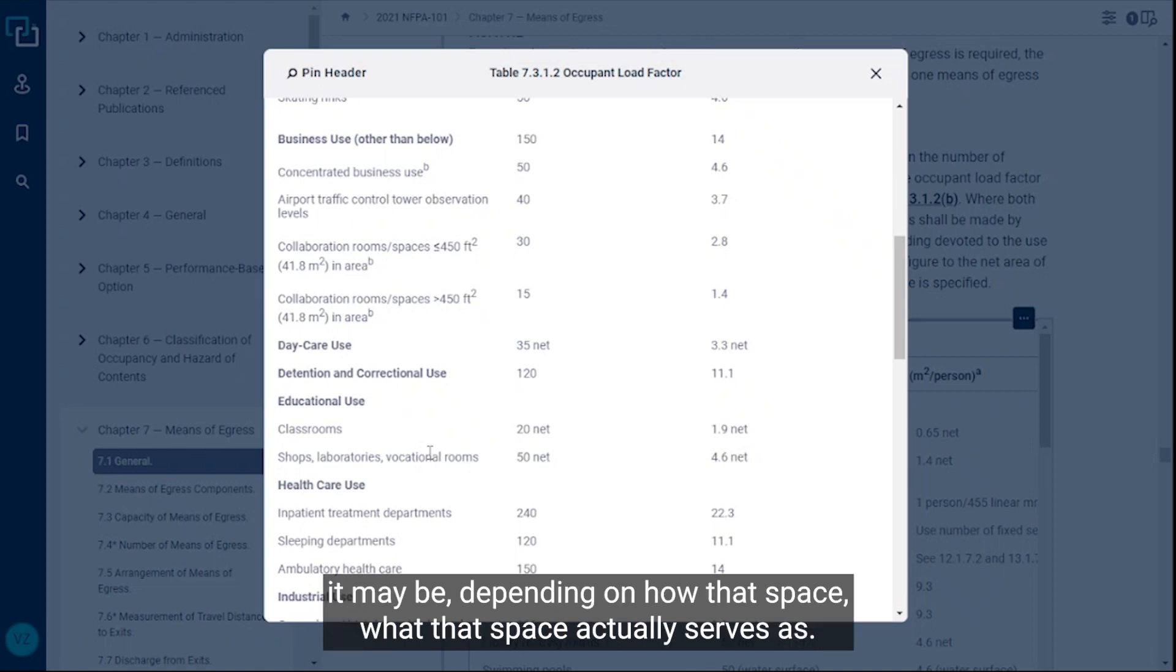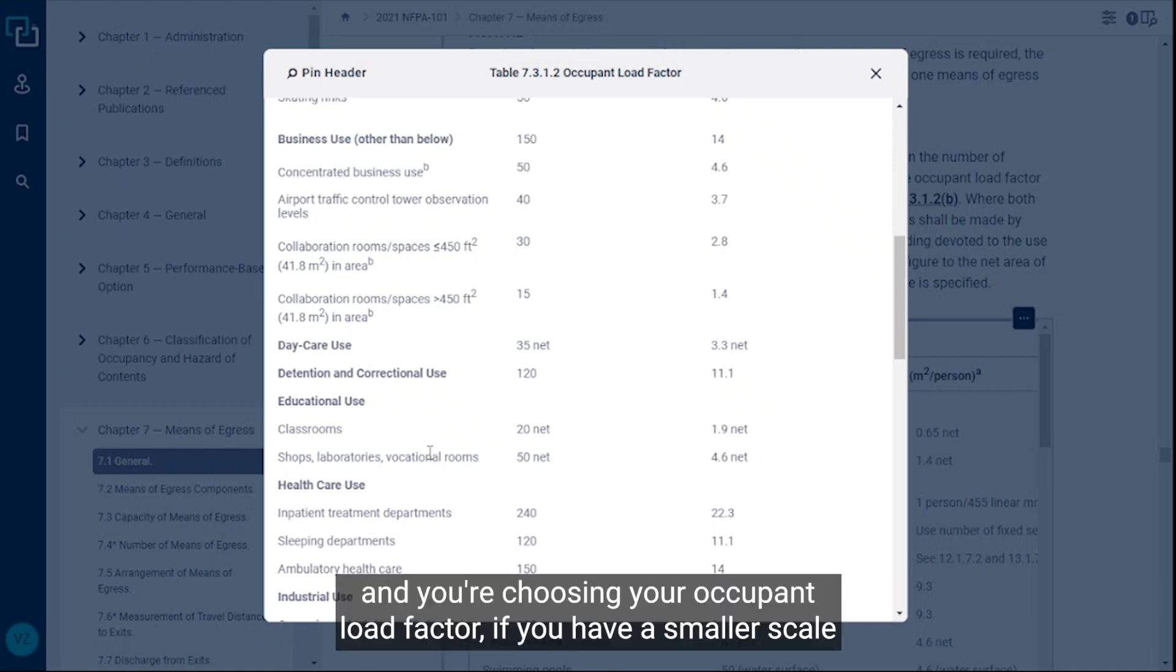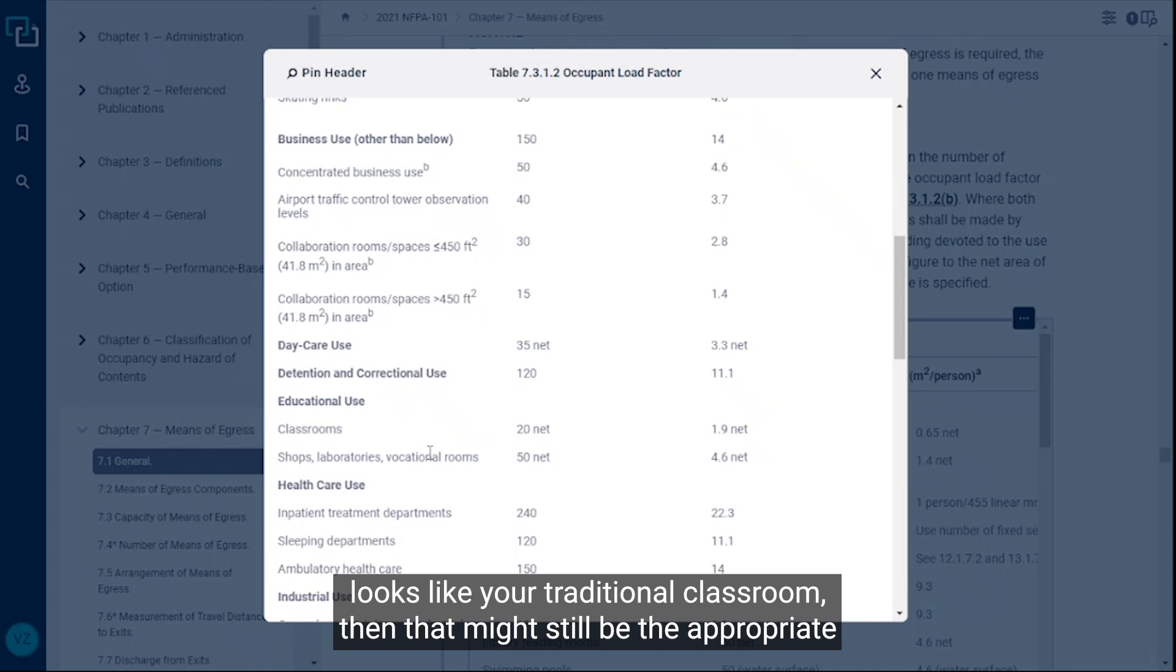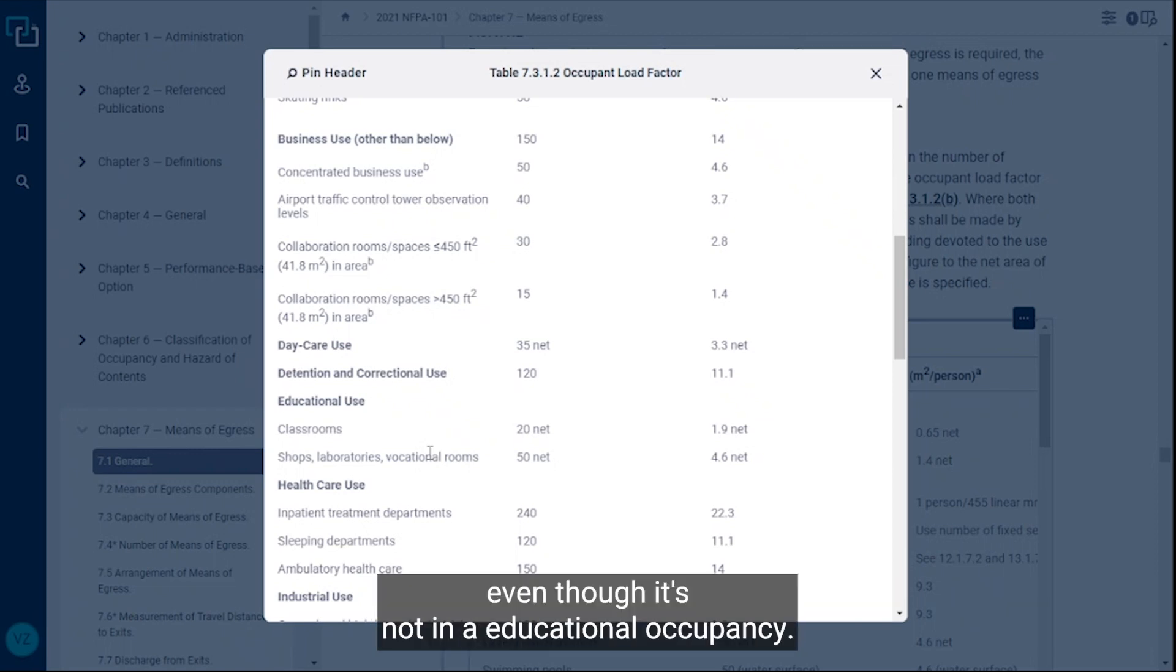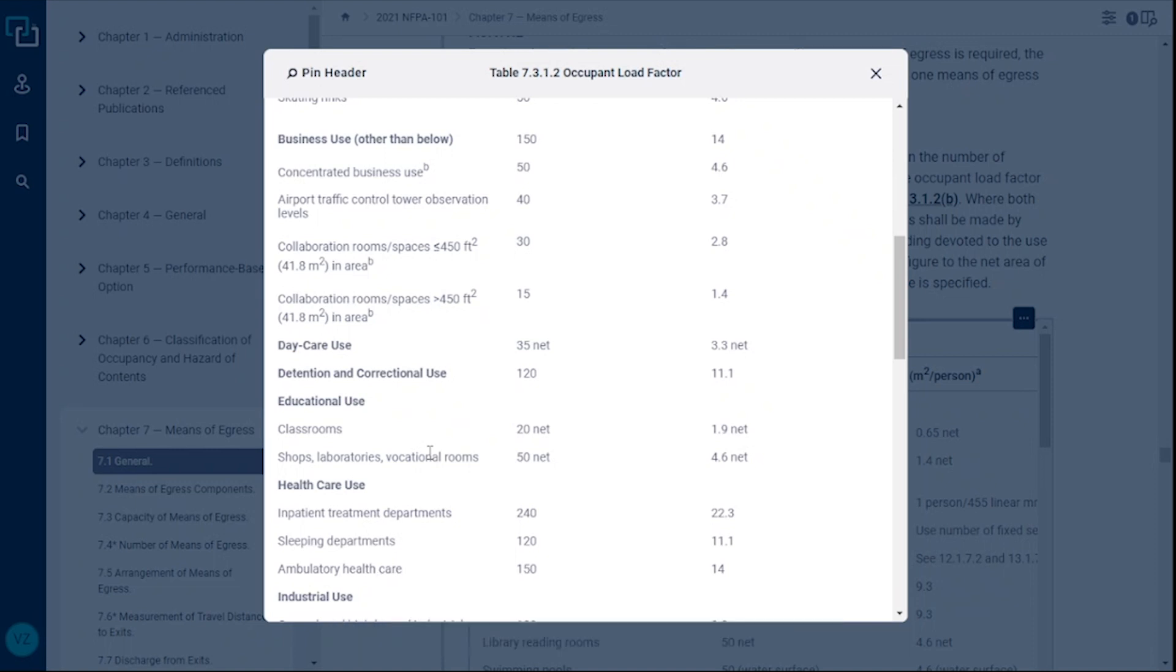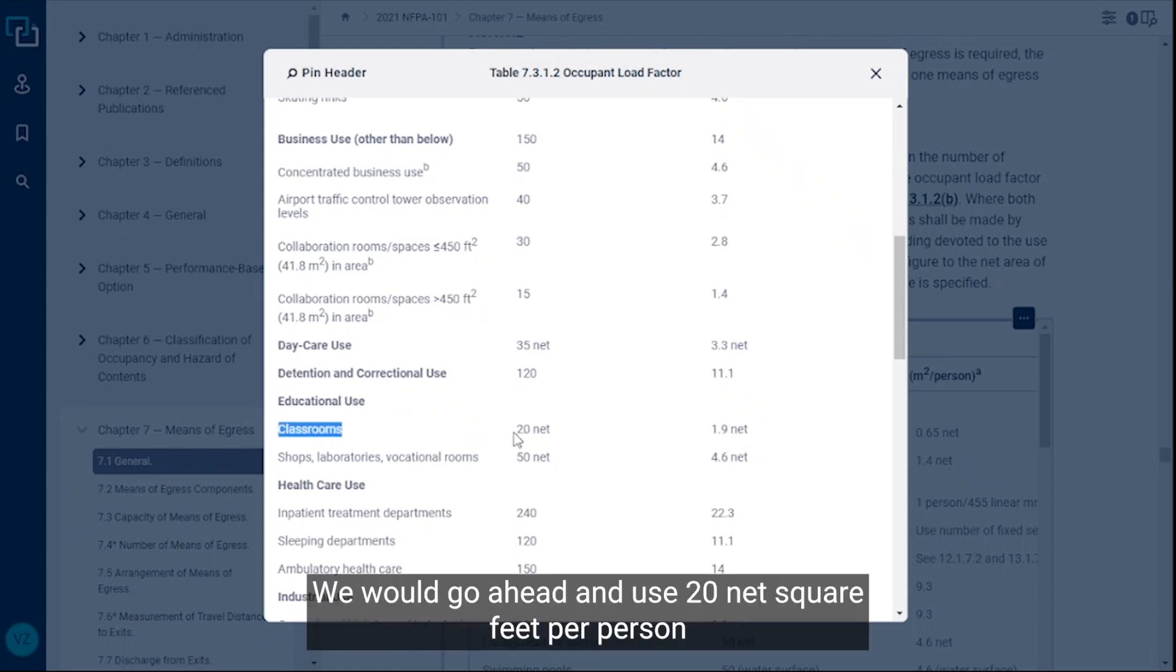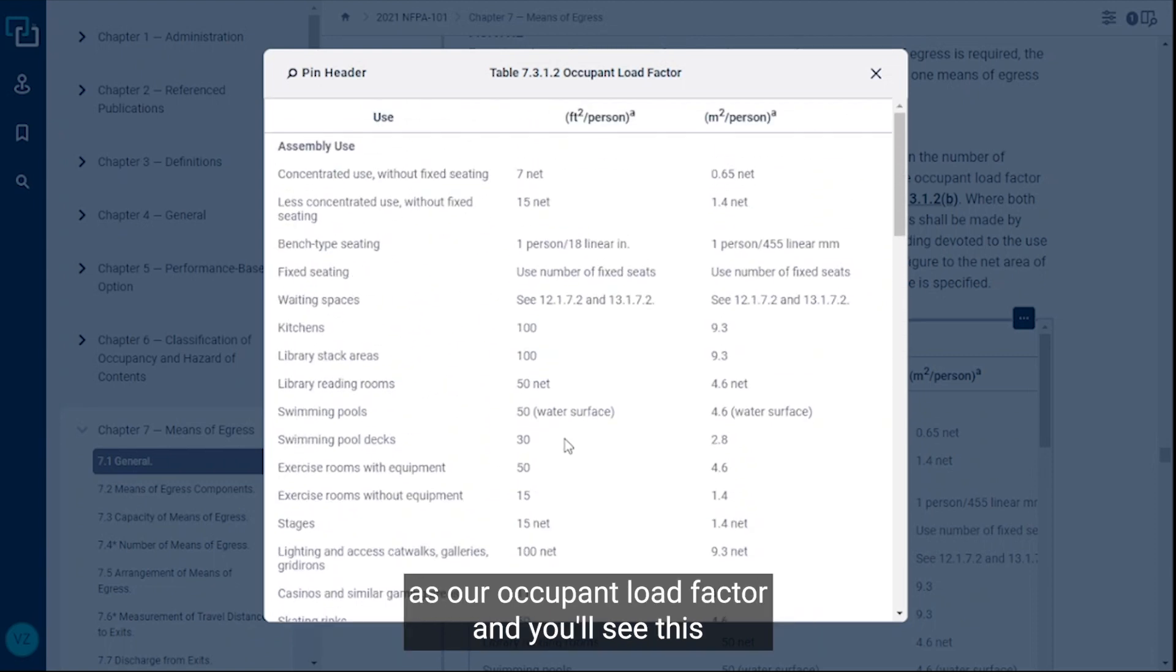However, when you're setting your occupant load and you're choosing your occupant load factor, if you have a smaller scale classroom that has let's say desks and a spot for a teacher and looks like your traditional classroom, then that might still be the appropriate occupant load factor for that space even though it's not in an educational occupancy. That's what I really wanted to stress. Here you'll see, let's say that was the case, we had a classroom. We would go ahead and use 20 net square feet per person as our occupant load factor.